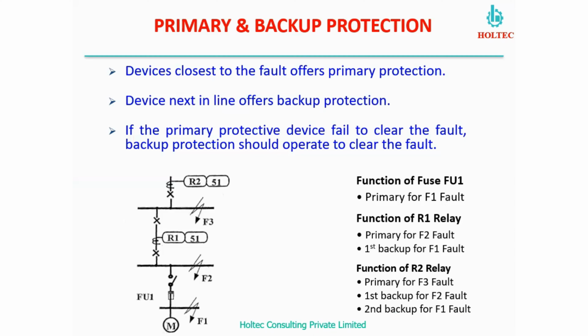And for those things we have to have a proper coordination, so that there are no incidents where, if fault F1 has happened, either relay 1 or relay 2 clears the fault before FU1 acts, which means a bigger zone of healthy equipment also will be affected. So this is the meaning of relay coordination. This is basically the purpose of the relay coordination.